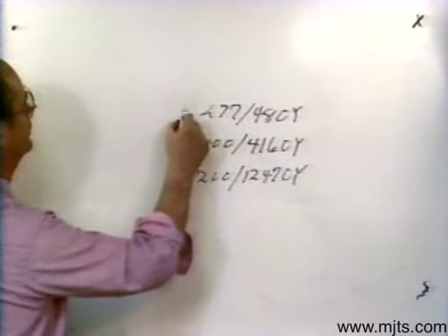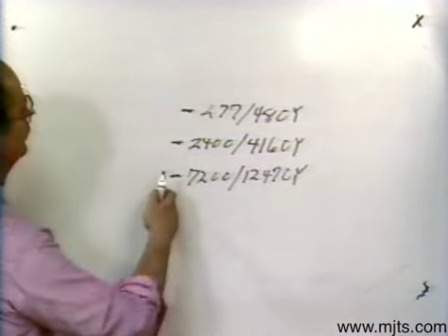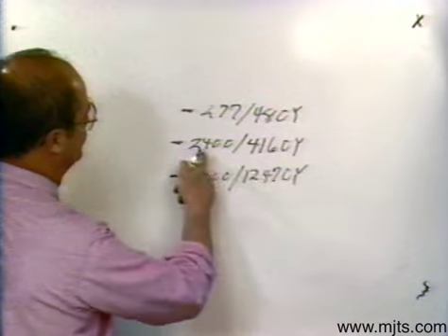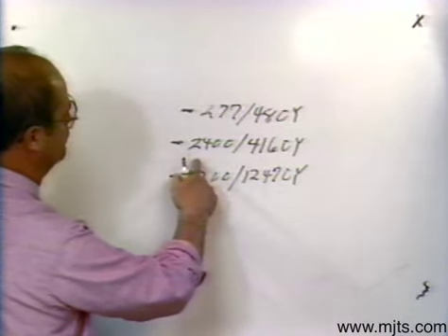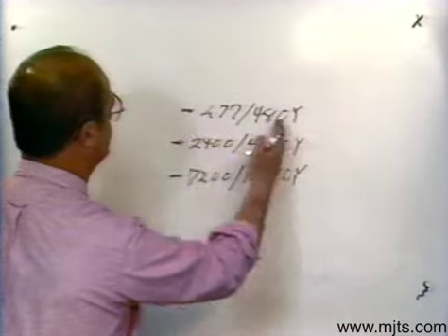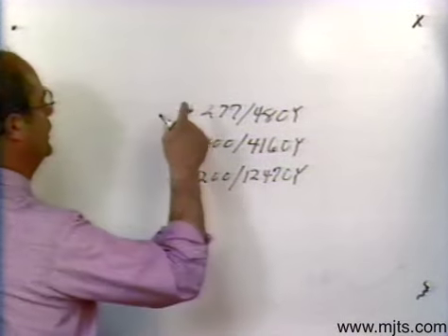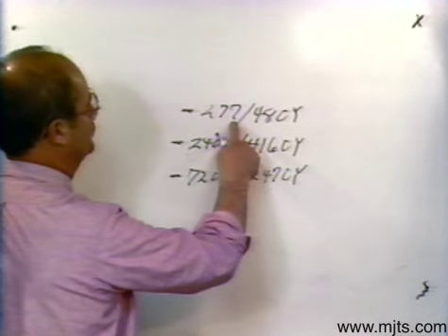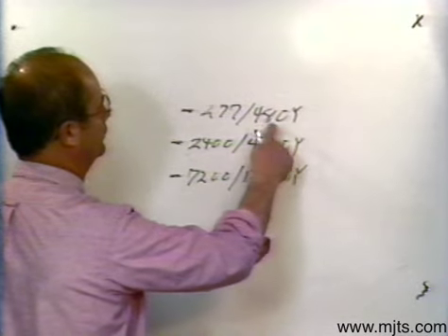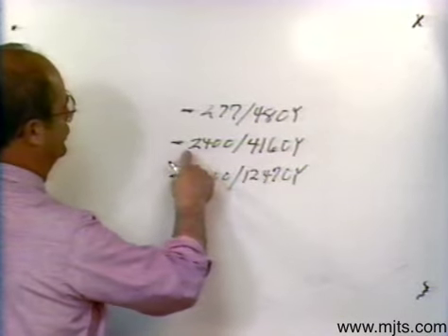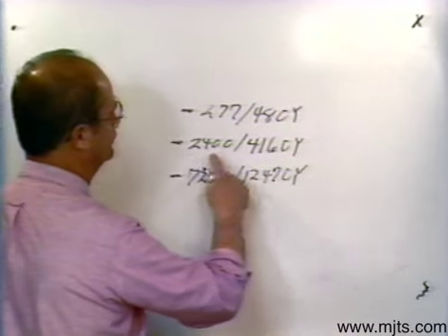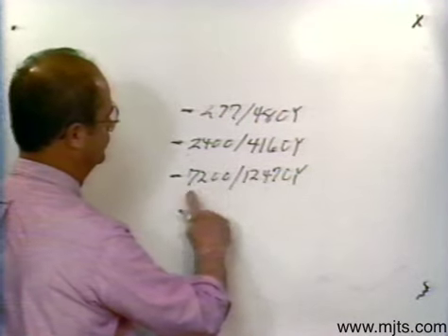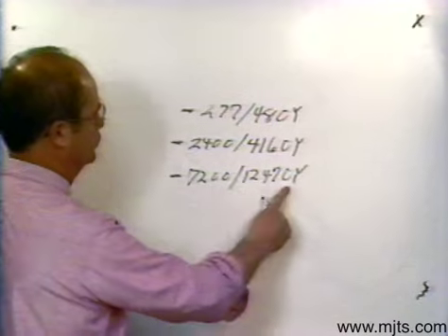This is a low side rating — our hyphen is out front. These transformers are more apt to be used in a substation. The way you read this is: if I delta connect this side, I would have 277 volts; if I Y connect, I would have 480. On the 2400/4160Y transformer, delta connect gives a 2400 volt system, Y connect gives 4160. And for 7200/12470Y, delta connect gives 7200 volts, Y connect gives 12470.